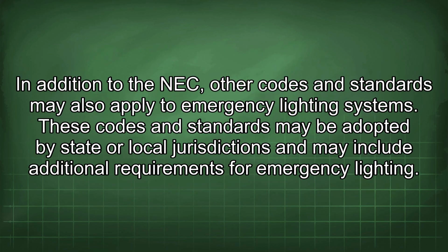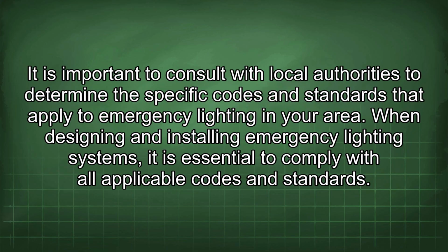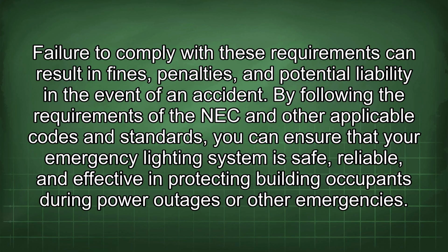In addition to the NEC, other codes and standards may also apply to emergency lighting systems. These codes and standards may be adopted by state or local jurisdictions and may include additional requirements for emergency lighting. It is important to consult with local authorities to determine the specific codes and standards that apply to emergency lighting in your area. When designing and installing emergency lighting systems, it is essential to comply with all applicable codes and standards. Failure to comply with these requirements can result in fines, penalties, and potential liability in the event of an accident. By following the requirements of the NEC and other applicable codes and standards, you can ensure that your emergency lighting system is safe, reliable, and effective in protecting building occupants during power outages or other emergencies.